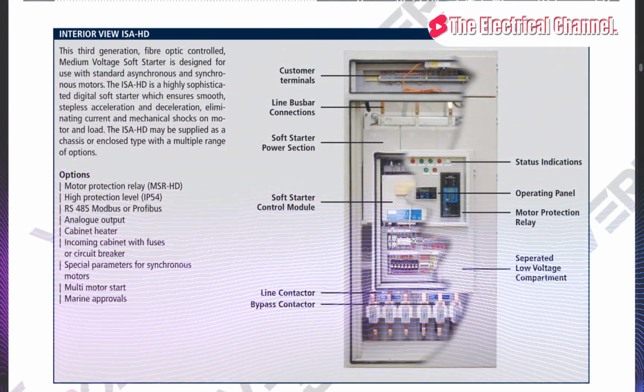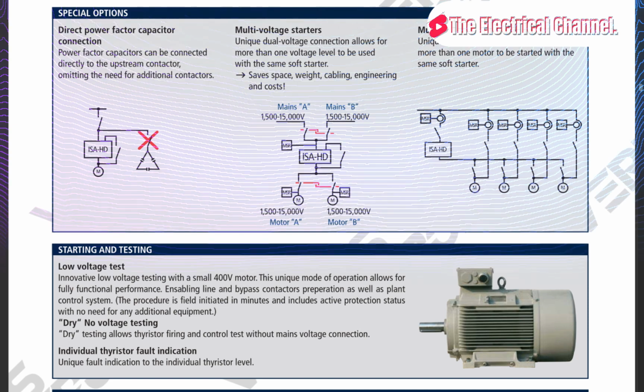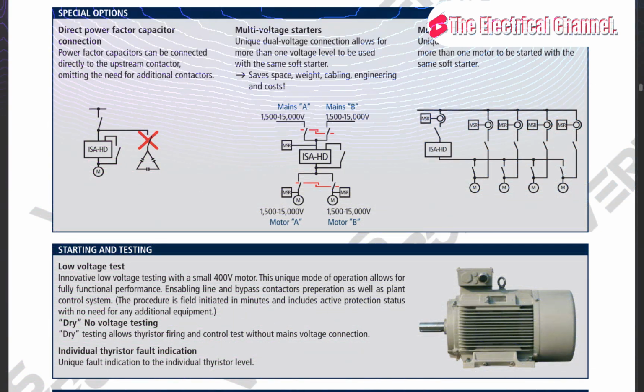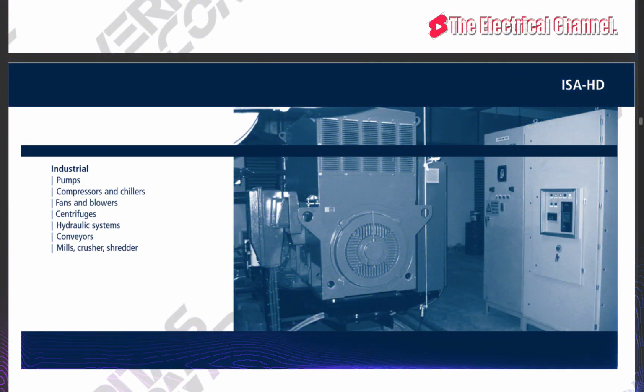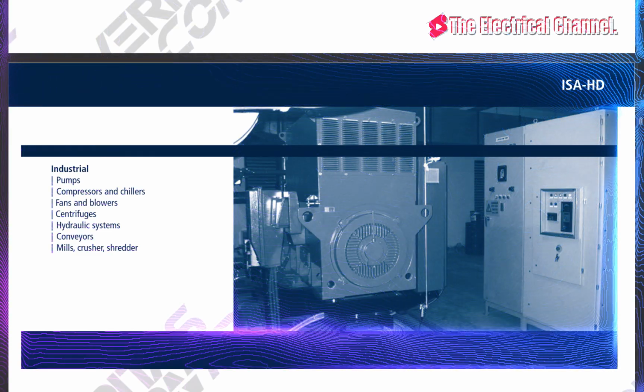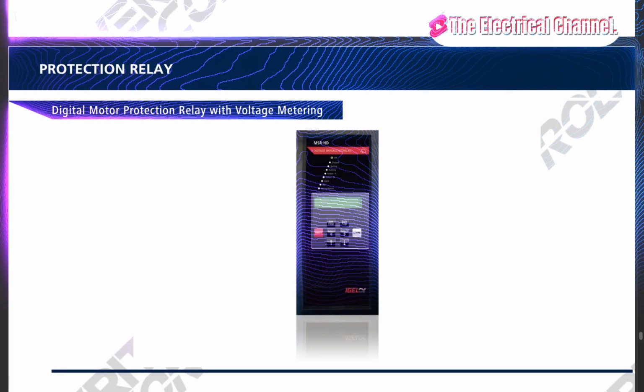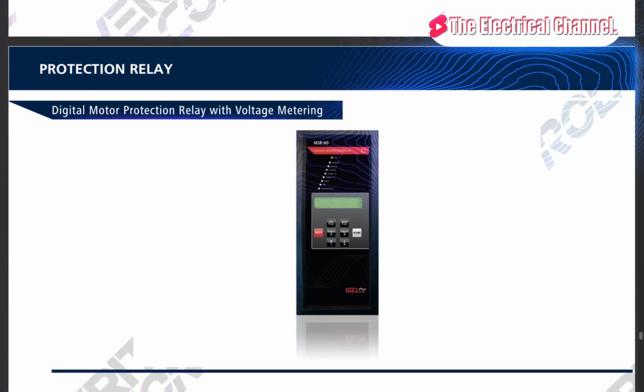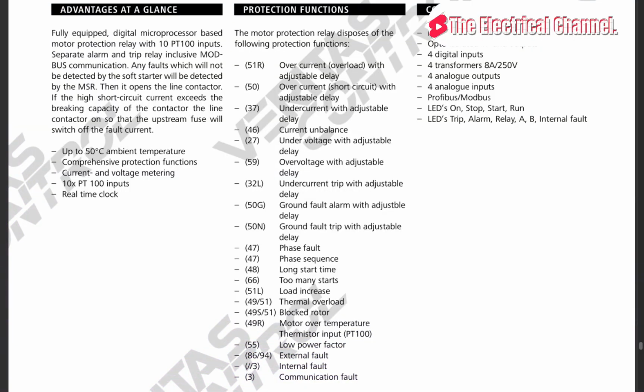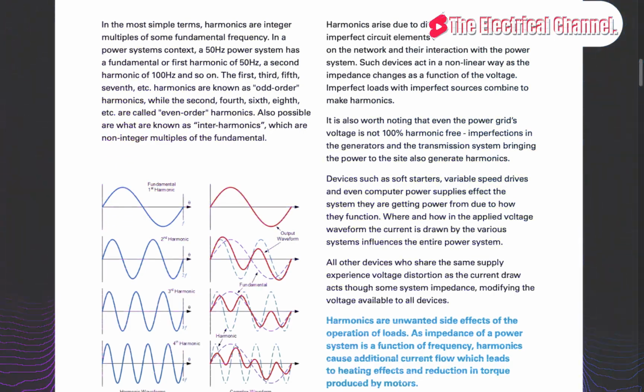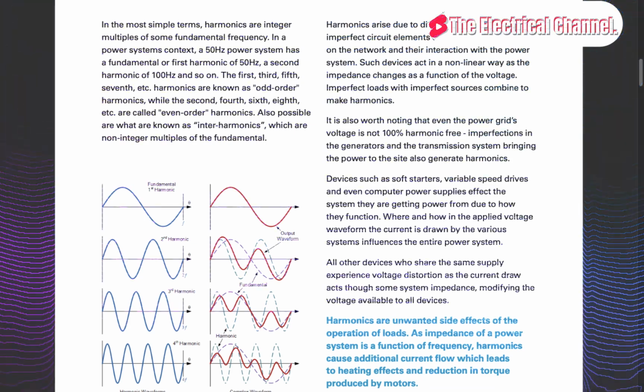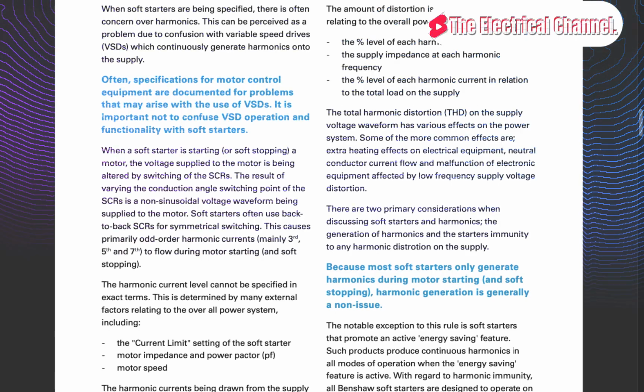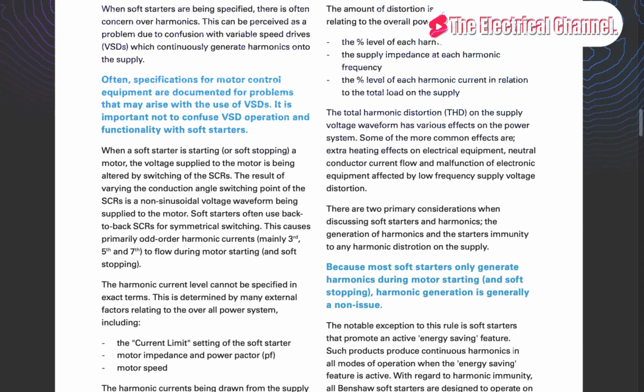In this solution, the third phase is just passing through the soft starter without controlling the voltage or the current. A soft starter controlling only 2 of the 3 phases is called a two-phase control soft starter, and it will function in the same way as a 3-phase control soft starter with a few exceptions. First, it is not possible to connect inside delta.